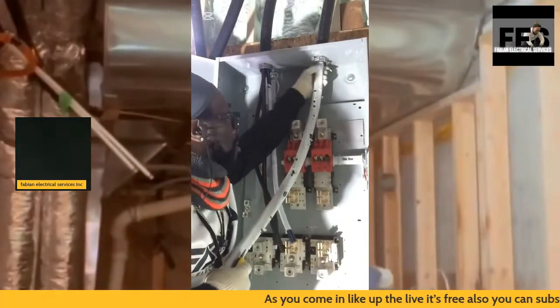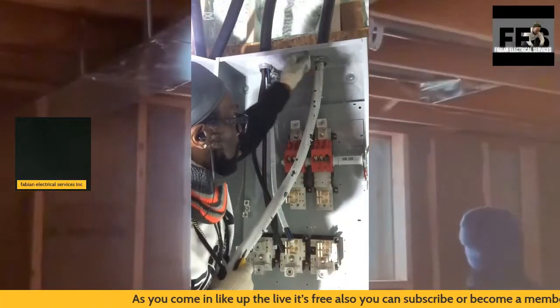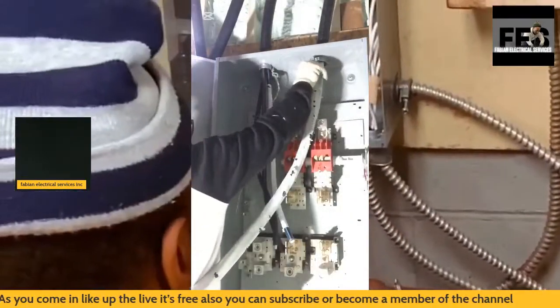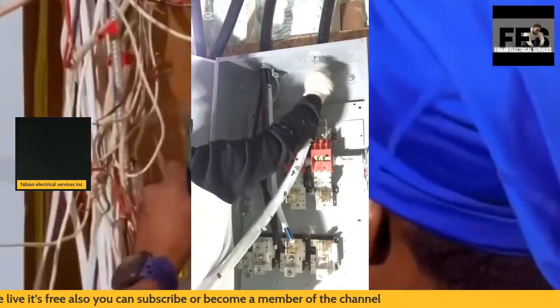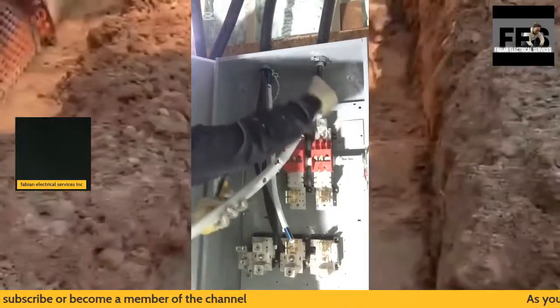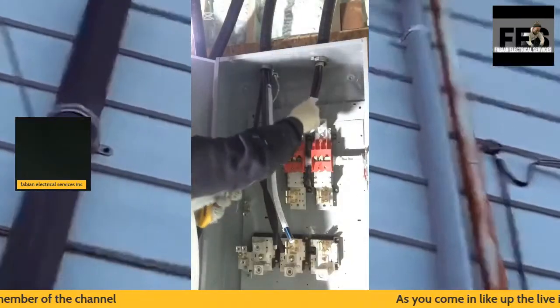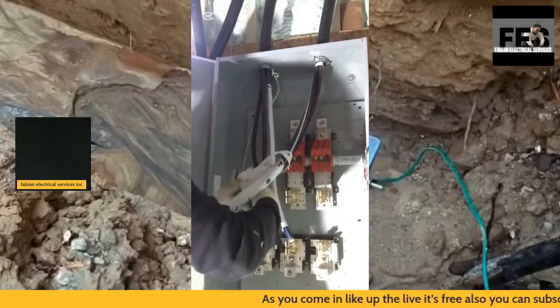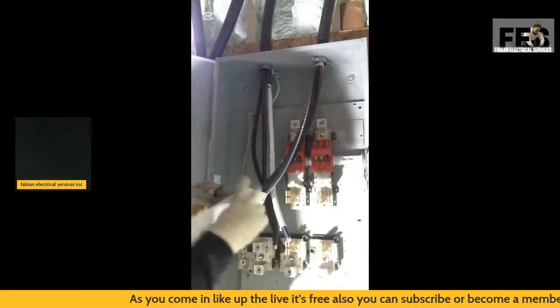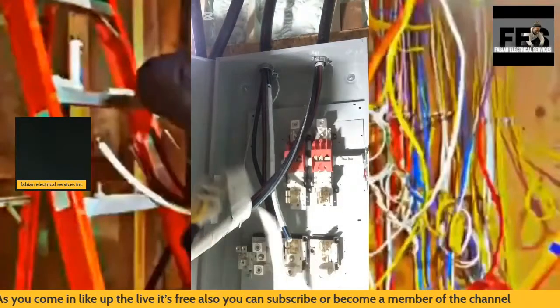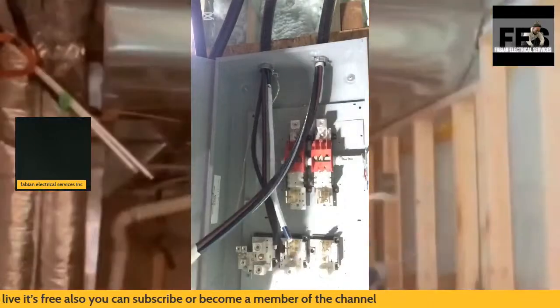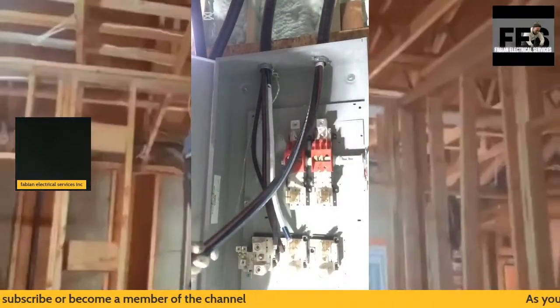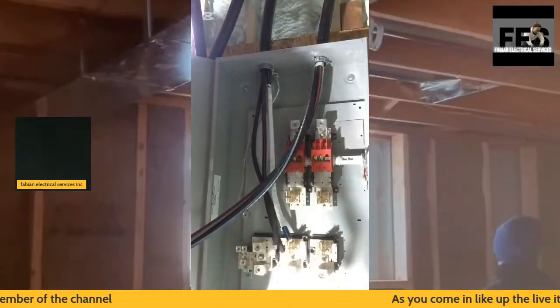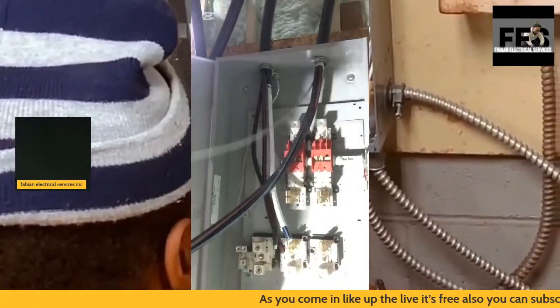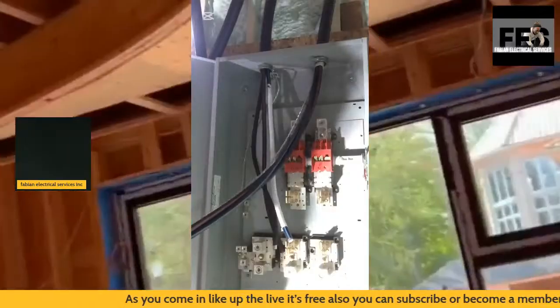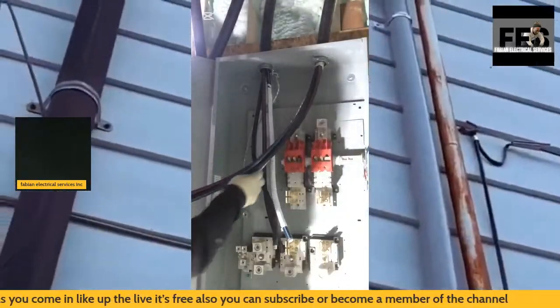But when it comes to any electrical installation that's more than 5 feet away from the actual electrical disconnect that's located outside of the home, it has to have a means of disconnect. So the main electrical 400 amp panel is located inside of the electrical room, inside of the basement of the home, and it's more than 40 feet away from the meter base. So the reason is I have to install my disconnect per code to stay within my electrical code compliance.